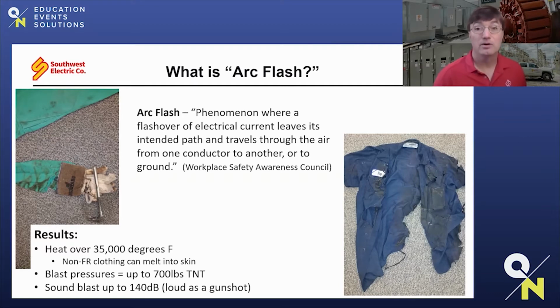The gentleman on the right was a contractor we hired in order to install some conduit. He thought the panel board he was working on was also de-energized. It was not. And a piece of metal that he dislodged fell across the live terminals and ground, also causing an explosion. You can tell one side of his shirt is burnt and tattered because that was the half of the shirt that was exposed to the front of the panel board. Fortunately, he was standing on the side, so his entire body was not burned, but he also experienced significant burns all over his torso. Fortunately, he also survived, but both of these gentlemen experienced life-altering events.